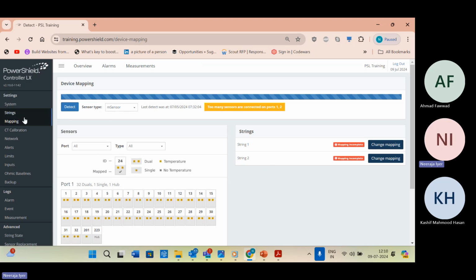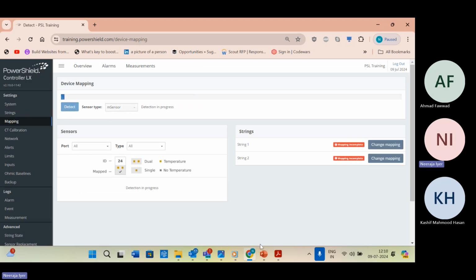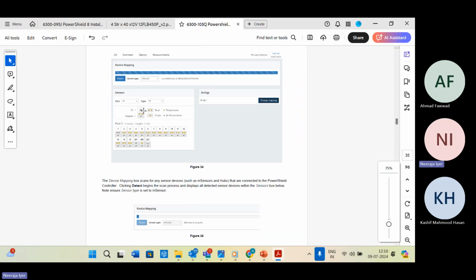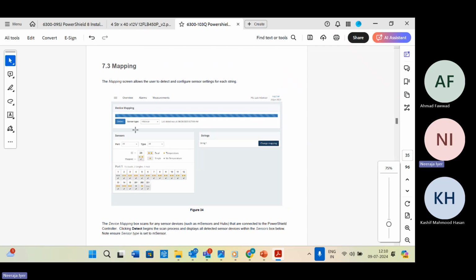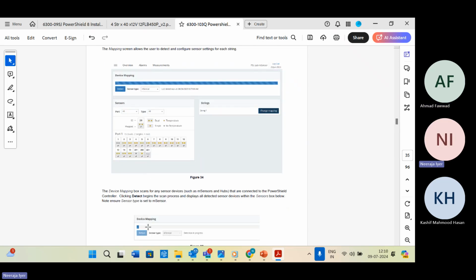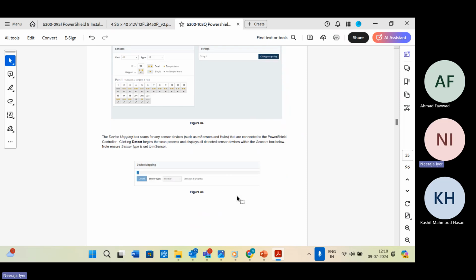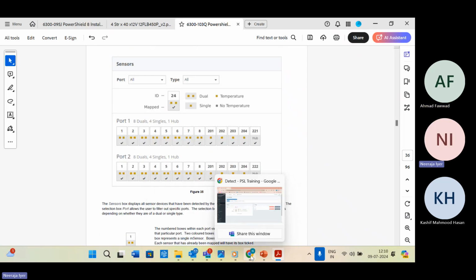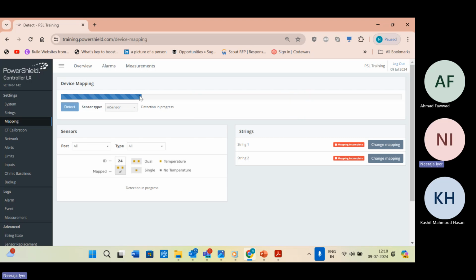The first thing to do in mapping is to press the detect button. While this is going on, I'll quickly jump into the manual for you to see. In the mapping section, the first thing you do is press the detect button. It is given very clearly with screenshots in our manual, whatever I'm doing. There is a progress bar that progresses. We just wait for a couple of minutes, just 1 minute. The reason I'm asking you to do 2 strings of 40 is that any communication issue, any B-bus interconnect issue, any sensor ID issue, whatever it is, will come out in this.